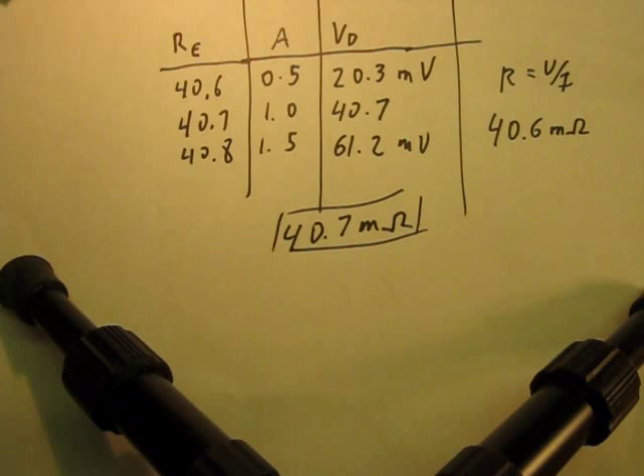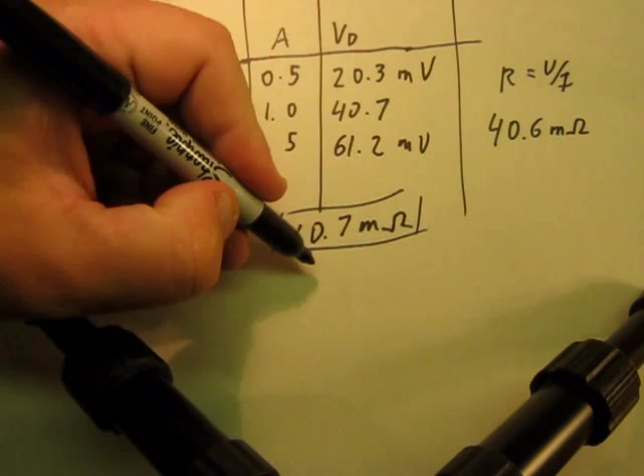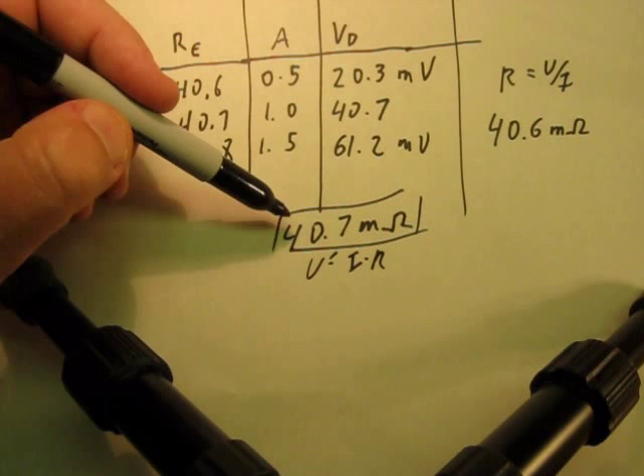For example, if you have 10 amps through this meter, you're going to drop 407 millivolts, because V equals I times R. And so you just move the decimal over if it's 10 amps. And that's actually 4 tenths of a volt, which actually is quite significant. So that's something you have to be really aware of when you're using a multimeter to measure current.